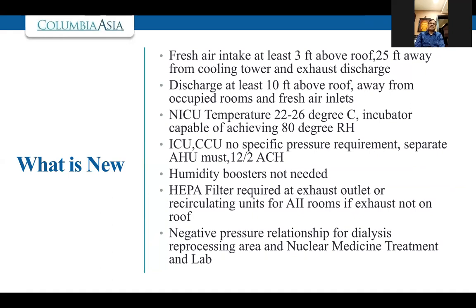NICU temperature, generally we should have more than the usual temperature requirements. The humidity requirements need to be higher, 80 percent RH. It is different from the operation theater RH. ICU changes, 12 air changes is sufficient. Humidity boosters are not needed specifically for ICUs and various other areas. And now ASHRAE has also brought down the requirement of humidity boosters specifically for operation theaters. A HEPA filter is required at the exhaust outlet if the exhaust is not on the roof.